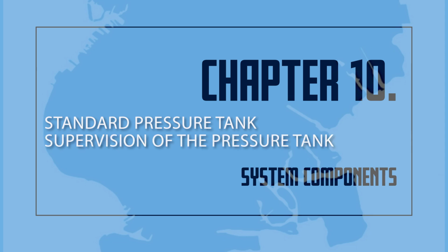Supervision of the pressure tank. The pressure tank may also be supervised by an approved central station company which monitors the entire sprinkler system. Supervisory devices are installed in the pressure tank. These devices alert the central station company when there is a problem with the tank's water level, air pressure, and water temperature. The devices also alert the central station company when water has been discharged from the tank.